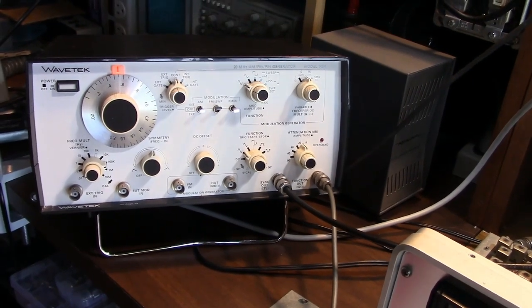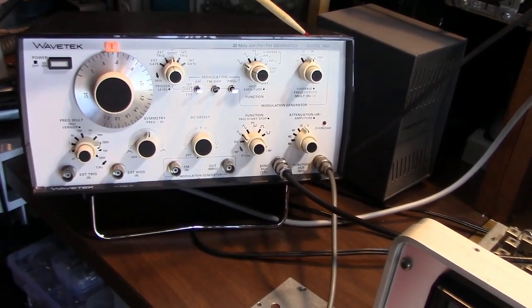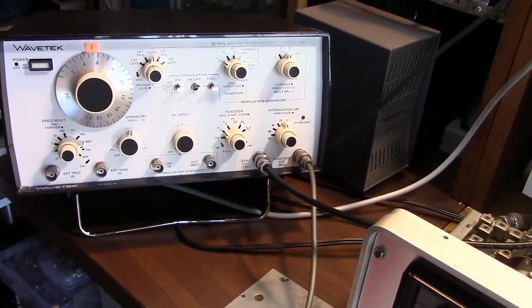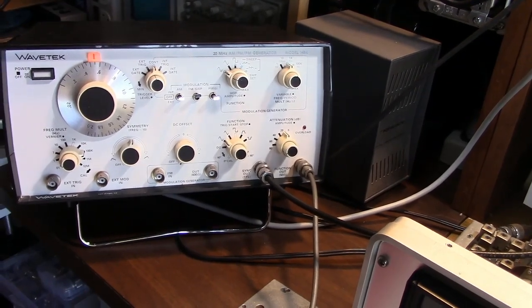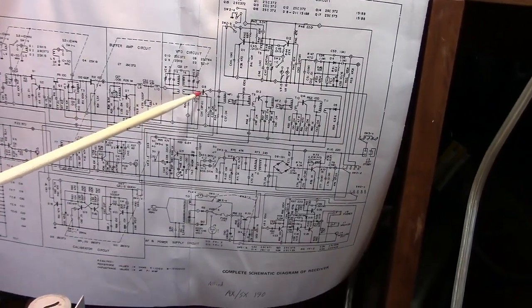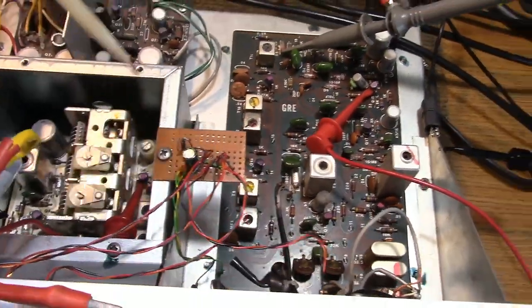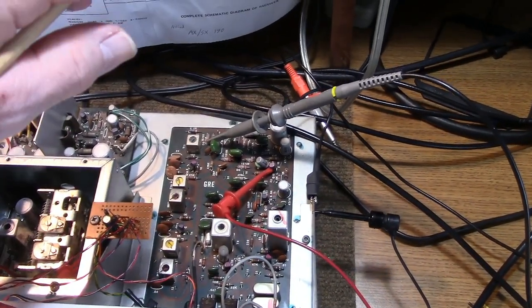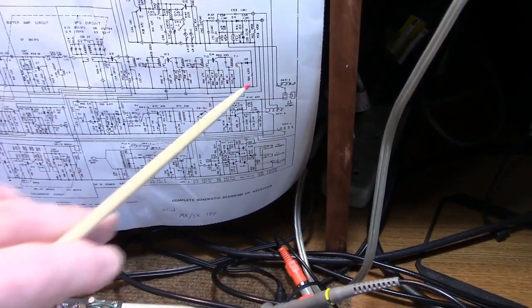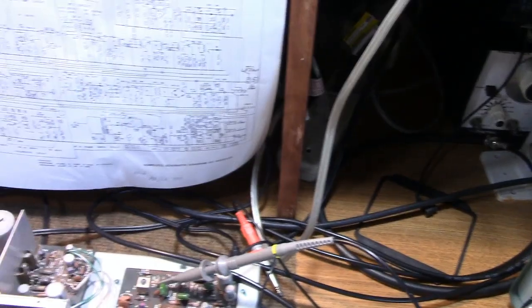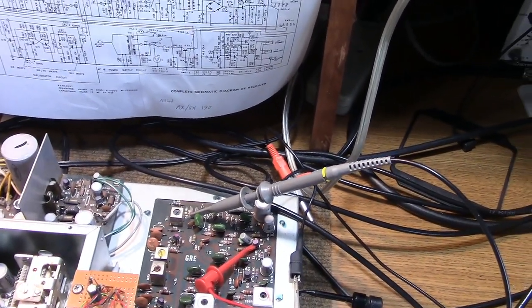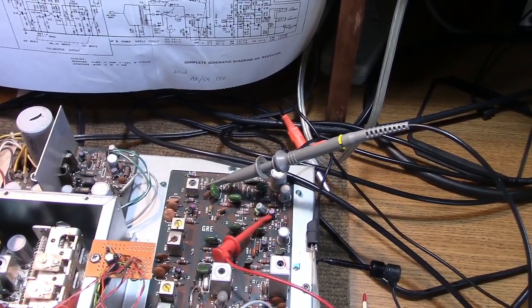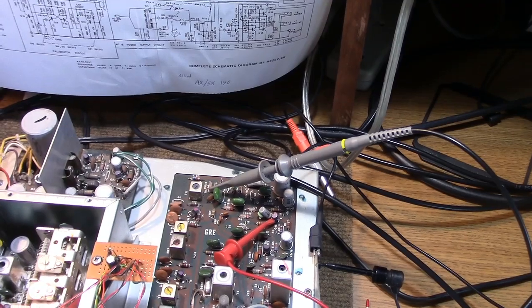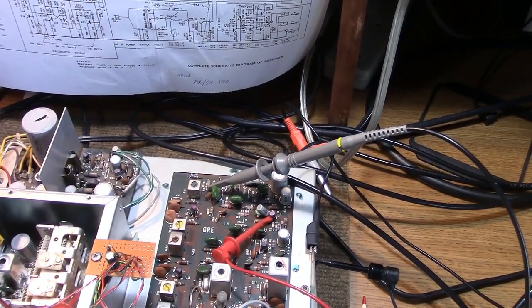I'm going to use a sweep generator to adjust the IF. I'm using a Wavetek model 148A, and I'm sweeping between 452 and 458, and I'm applying the output to the base of Q8, which is right here, and I'm measuring at the cathode of the detector diode, which is right here. And according to the instructions in the alignment of the second IF, you tune MF1, T9, MF2, and T10 and T11 for peak symmetry on the scope.